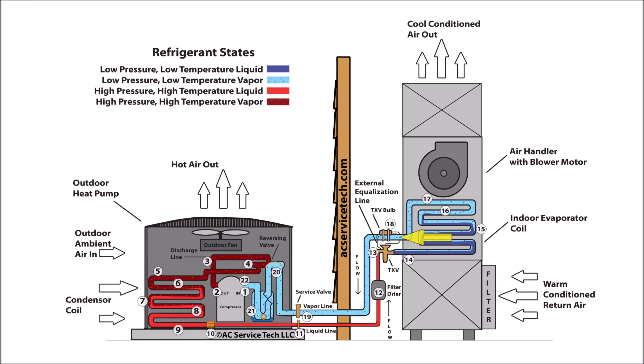The low pressure, low temperature, superheated vapor travels to the vapor service valve at step nineteen. This is where you can read the low pressure, low temperature vapor pressure, and also where you can check the total superheat of the system. The temperature increase of the vapor refrigerant between step sixteen and step nineteen is referred to as the total superheat.